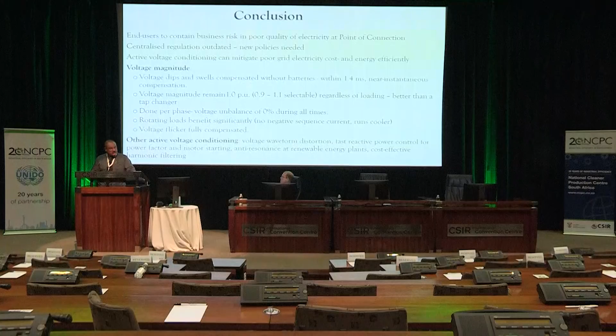So although the future seems not too exciting in terms of what is happening in our networks, I perceive the most important message of this afternoon is that solutions are available without the expense of a normal UPS and the maintenance requirements of batteries, where one can condition the voltage to a sufficiently good level, for equipment connected up to a few MVAs, up to 22 kV - but that's not really necessary. One should rather distribute these kinds of solutions throughout the plant and make sure sensitive equipment becomes predictable in terms of the scheduled production cycles.